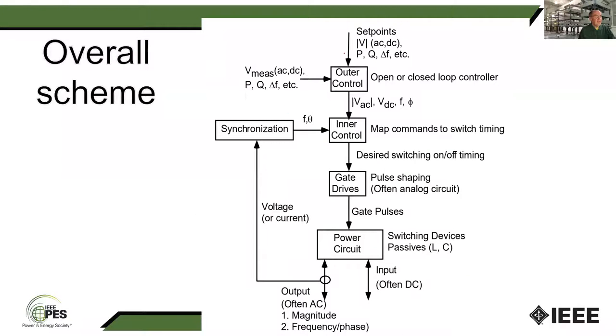And so the overall control scheme is, we start at the power circuit, these are our switching devices. We're gonna have an input and an output. We're gonna have a gate driver that turns the switches on and off. And then we're gonna have an inner control. And so these are the current regulators. And this is also gonna control the synchronization to the power system to follow the power system frequency. And then there'll be an outer control loop that does things like real power control or reactive power control based on set points. And we'll talk a little bit about each of these as we go.